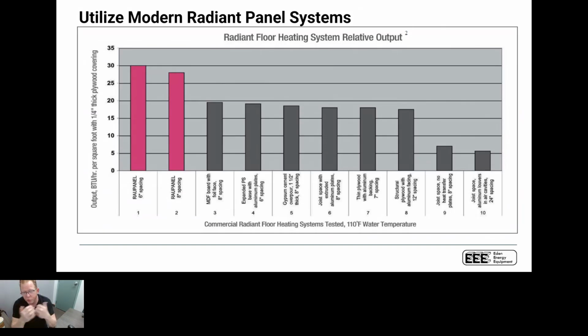One of the other things that's really, really cool, and I've done this in my own home, is if we start to use some of the new dry panel systems that are made by manufacturers like Uponor and Rehau and Heatlink and others, they have some really cool aluminum panel systems that can deliver a lot of BTUs. And I had a picture of one in the previous slide. So if you were to look at, for example, a Rehau panel system with 110 degree average water temperature, you can get 30 BTUs per square foot.